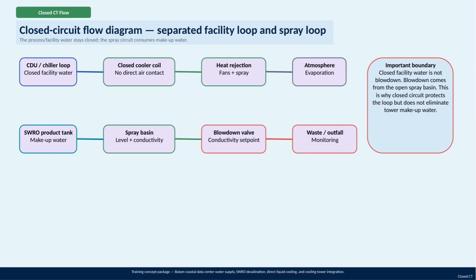Blowdown or wastewater discharge comes specifically from the open spray basin and not from the closed loop, regulated through conductivity set points and valves. The key point here is understanding that the closed circuit protects the internal cooling loop and water quality, but does not eliminate the need for tower makeup water because of evaporation losses in the open spray basin. This distinction is fundamental for water conservation and system performance.